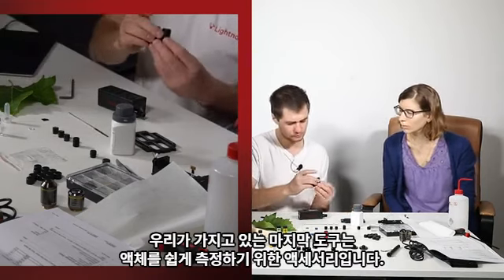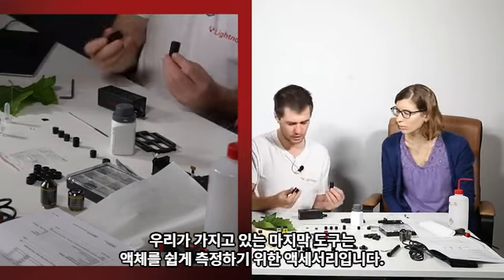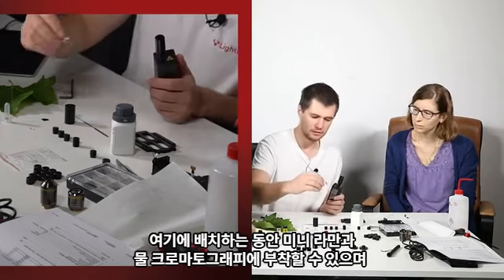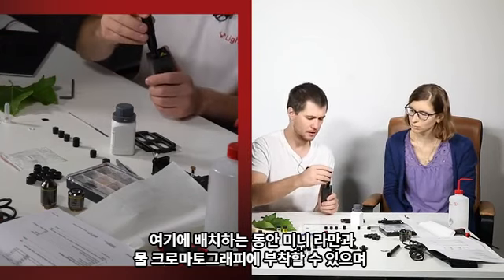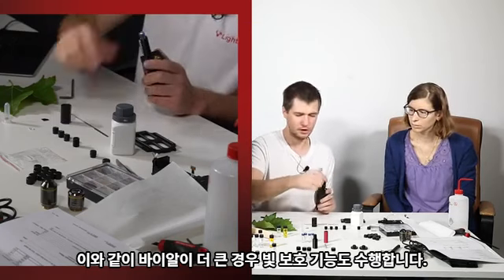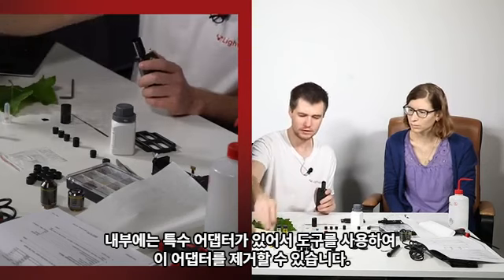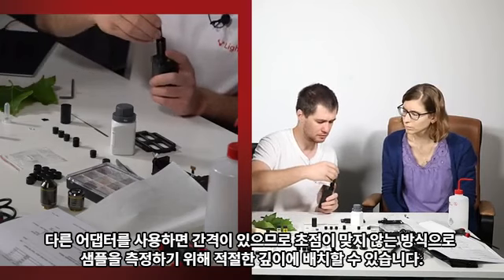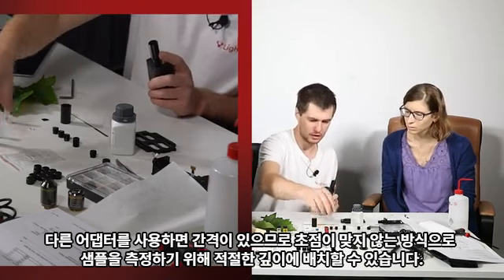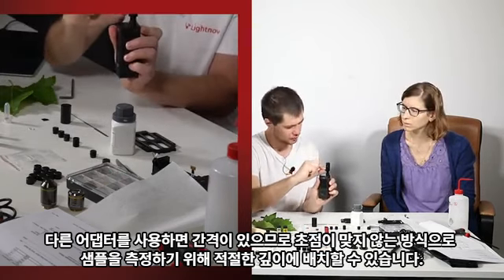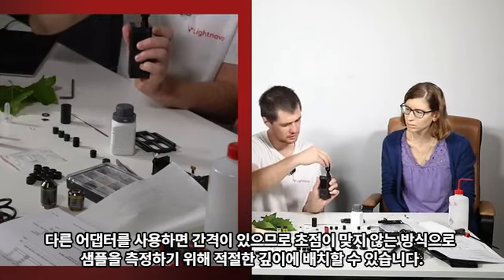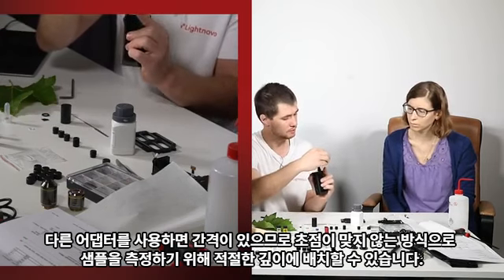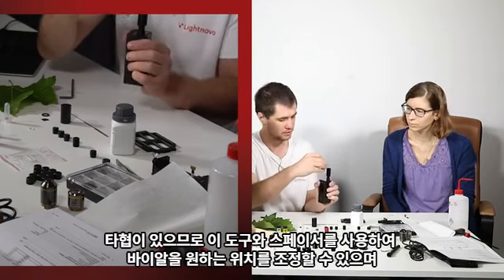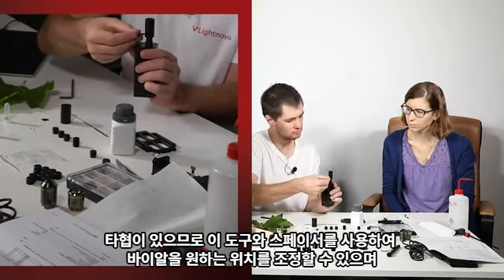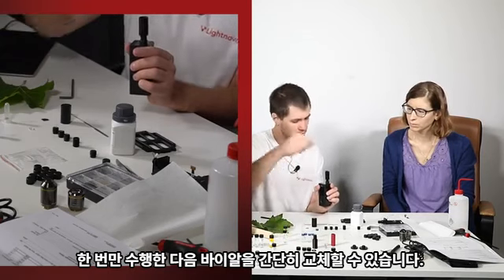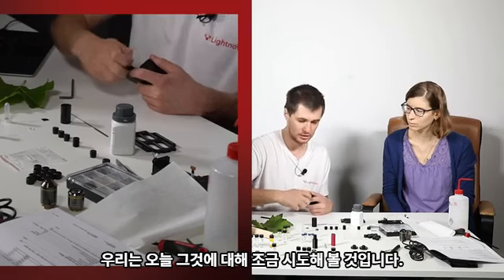The last tool that we have is an accessory for easy measurements of liquids. You also attach it to the miniRaman, and a chromatography vial, you place it here, and you also get light protection. If you have a larger vial like these ones, it won't fit, because inside we have a special adapter. So you can remove this adapter with the tool, yeah? Yes. And use another adapter. It's a spacer, so you can place the vial at the proper depth in order to measure samples in a way that your focus is not on the glass, but a little bit inside. If it's too deep inside, you also lose signal. There is a compromise. So you can, with this tool and spacer, adjust where you want your vial to be. And when you have done it one time, then you simply replace the vials and you can do routine measurements. And we will try a little bit of that today.